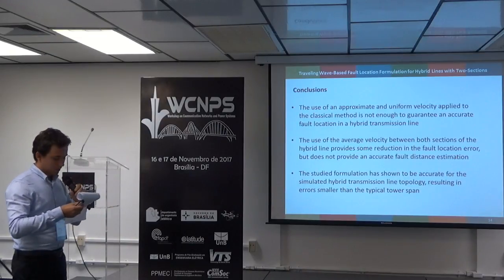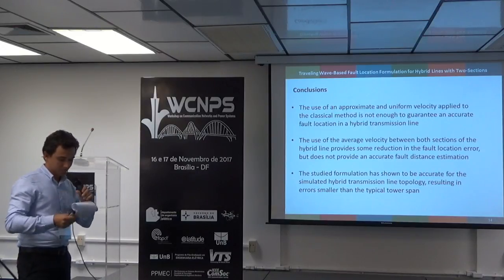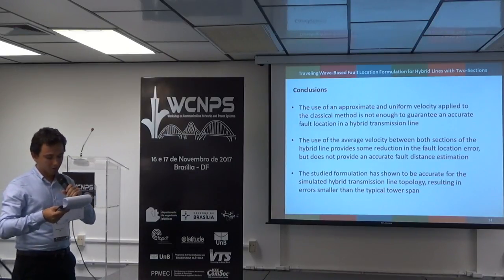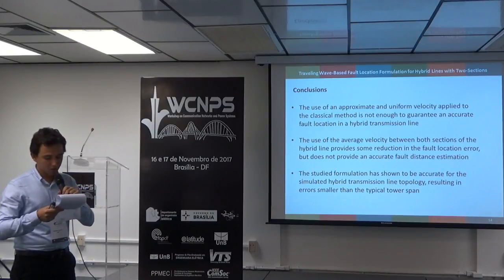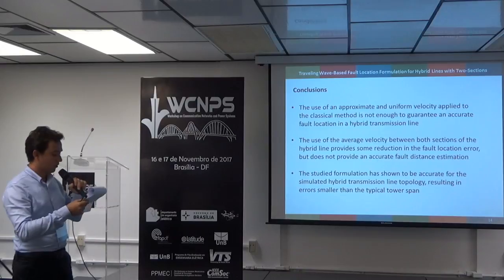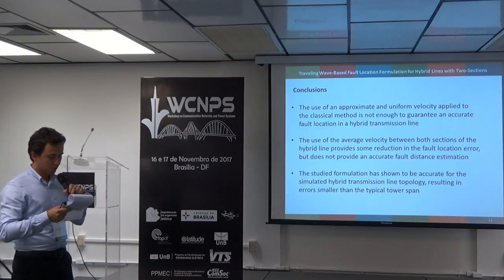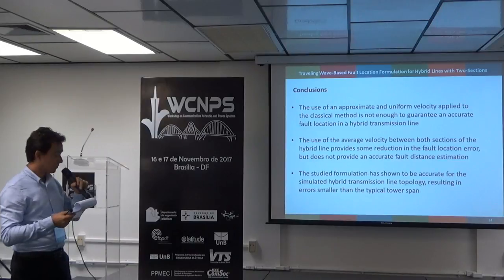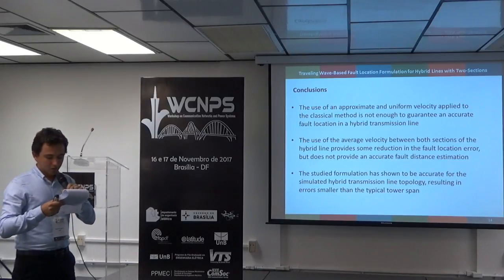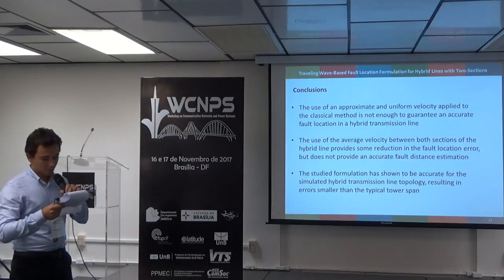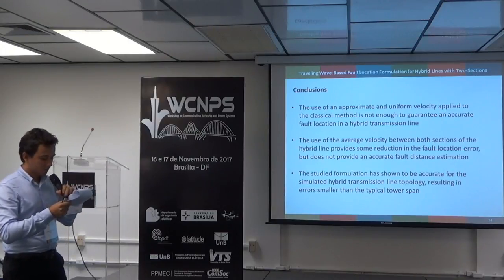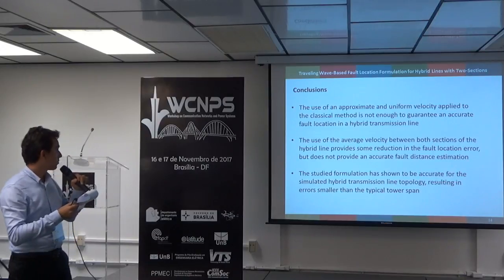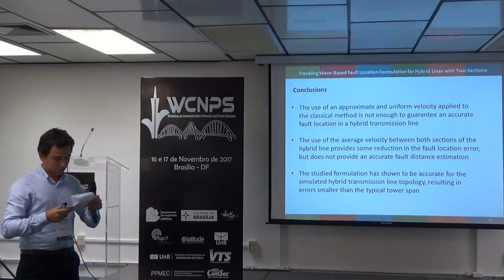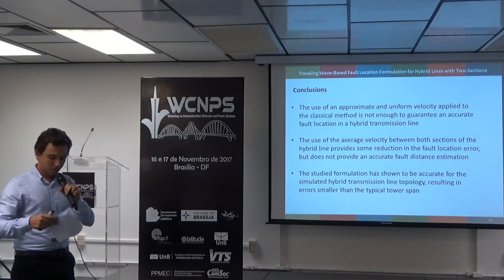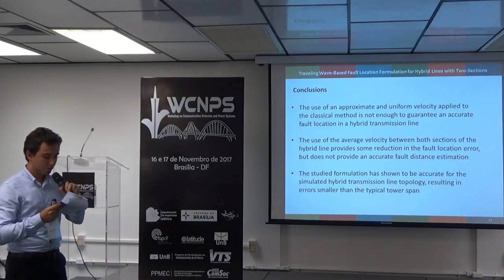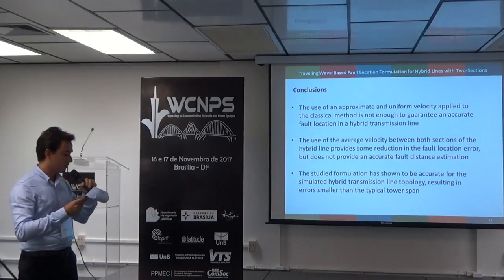So finally, the conclusions. The use of an approximate and uniform velocity applied to the classical method is not enough to guarantee an accurate fault location in hybrid transmission lines. The use of the average velocity provides some reduction, but does not provide an accurate fault distance estimation. And the studied formulation has shown to be accurate, resulting in errors smaller than the typical tower span.